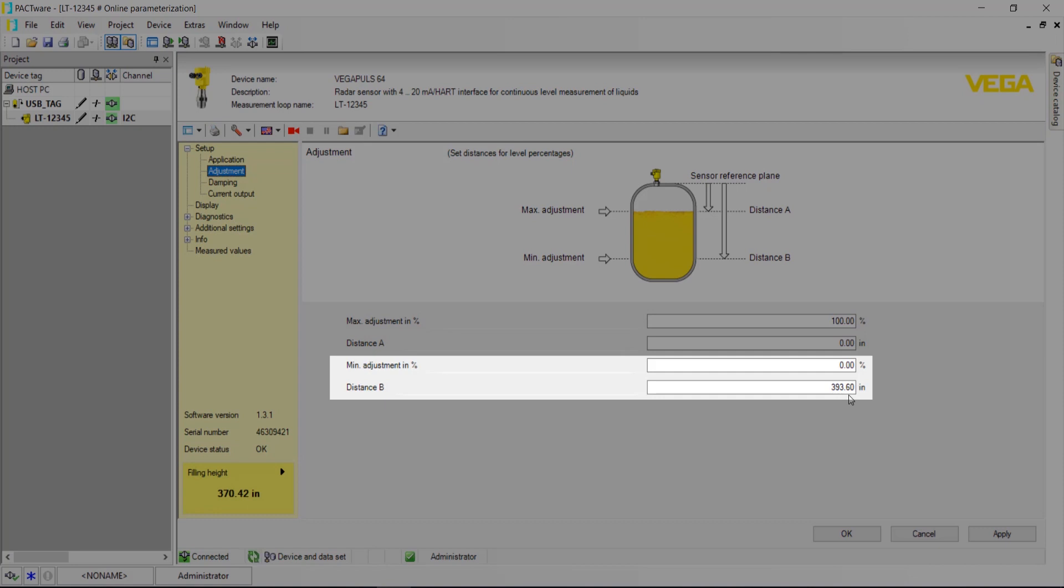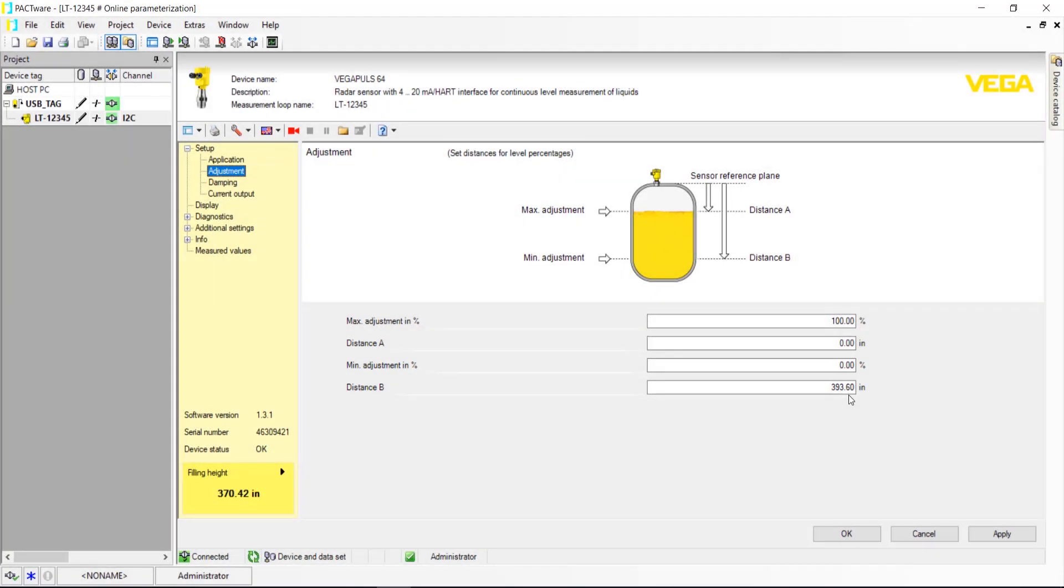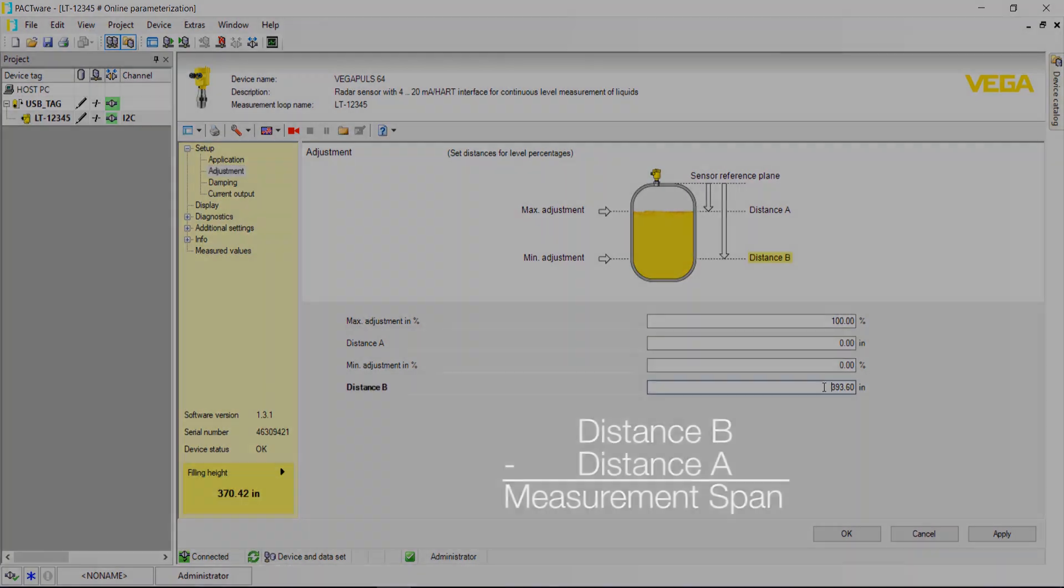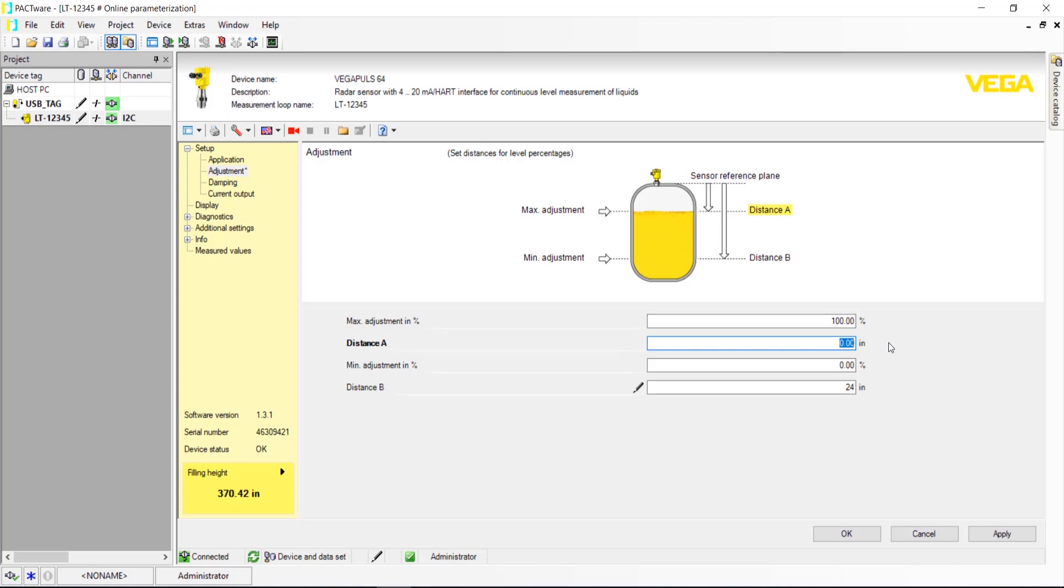Distance B is the distance from the radar reference point to the 0% fill point, or where the sensor will output 4 mA. This will be a larger number than distance A, and the difference between the two will be your entire measurement span. Once you've input your numbers, click Apply.